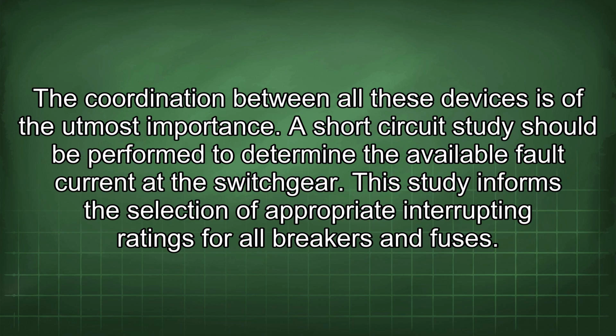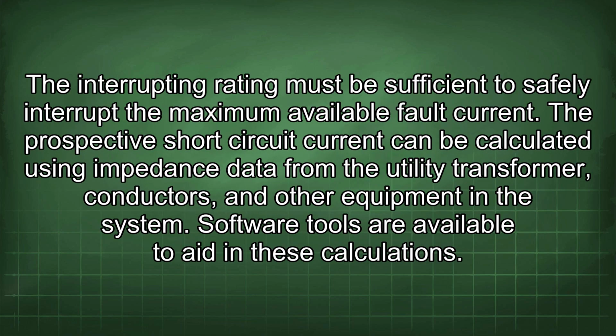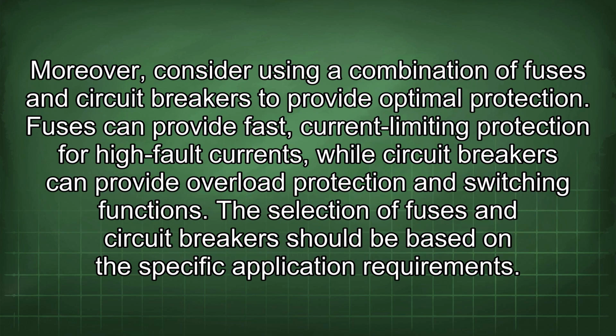A short-circuit study should be performed to determine the available fault current at the switchgear. This study informs the selection of appropriate interrupting ratings for all breakers and fuses. The interrupting rating must be sufficient to safely interrupt the maximum available fault current. The prospective short-circuit current can be calculated using impedance data from the utility, transformer, conductors, and other equipment in the system. Software tools are available to aid in these calculations. Moreover, consider using a combination of fuses and circuit breakers to provide optimal protection. Fuses can provide fast current limiting protection for high fault currents, while circuit breakers can provide overload protection and switching functions. The selection of fuses and circuit breakers should be based on the specific application requirements.